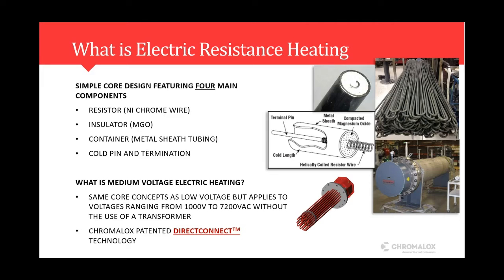But as simple as it is in concept, it's actually very versatile in how those elements can be used. You can see on the right-hand side there, you can bank multiple of these elements together to create very large loads, attachment fittings and tanks, vessels, you name it. So they're very versatile in that core technology. Now, typically what you see in the industry is low voltage technology, and that's basically anything that's rated up to 1,000 volts. But Chromalox has actually patented the first true medium voltage element, a while back, that's capable up to 7.2 kV. And we're going to talk about what really that is and why that drives the efficiency and the sustainability efforts moving forward.